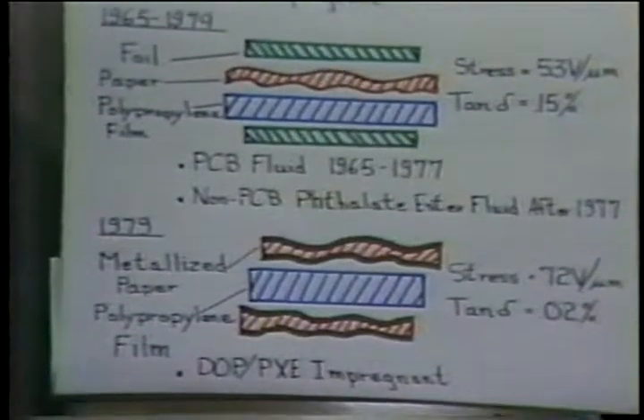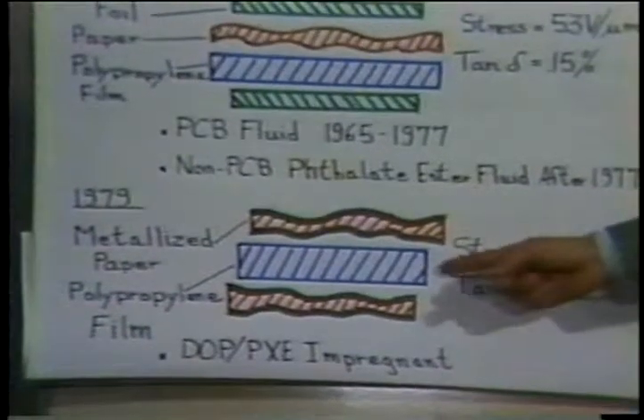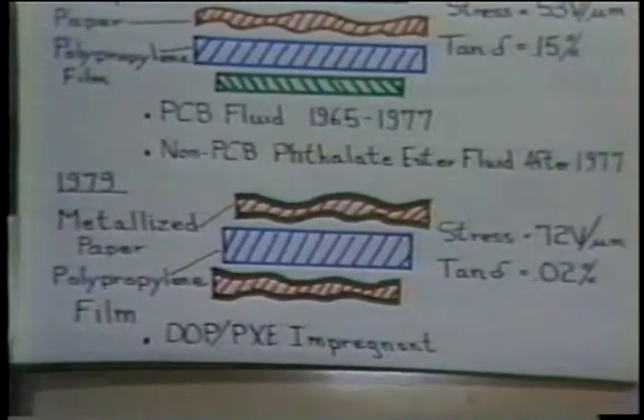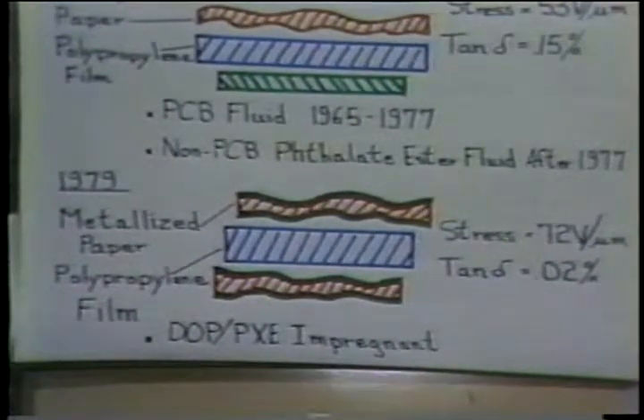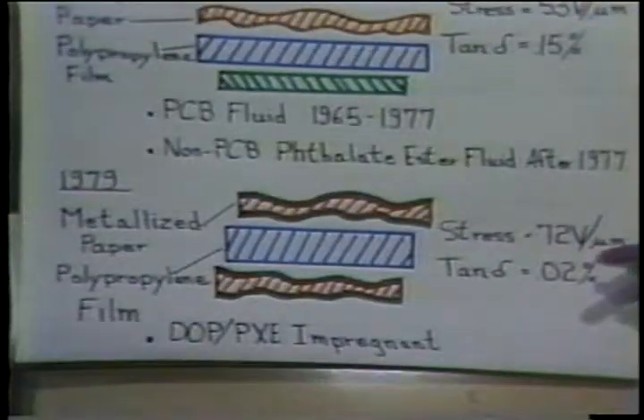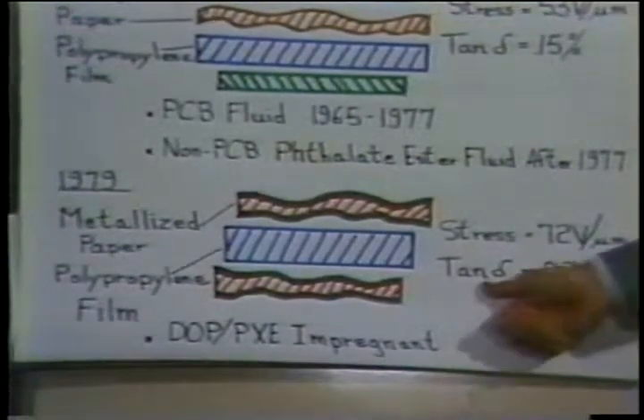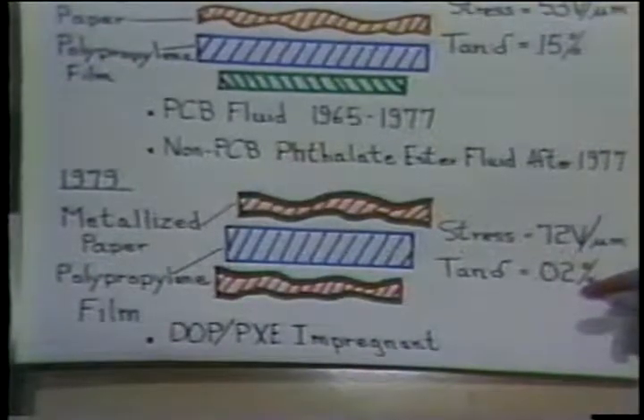In 1979, metallized paper and polypropylene film construction was introduced. Metallized paper allowed us to use a metallized construction and obtain the good clearability found with a metallized electrode. In addition, the rough surface on the paper allowed the full impregnation of this type of design. The stresses were increased up to 72 volts per micron. Again, because polypropylene was the main dielectric, the dissipation factor was 0.02%. The impregnant that was used in this design was dioctyl phthalate mixed with phenylxylyl ethane. This fluid had a low enough viscosity to fully impregnate this design, and yet had acceptable chemistry to aid the clearing process.